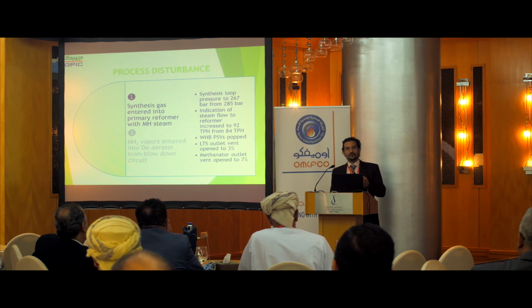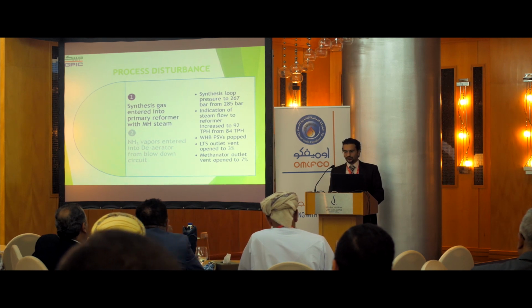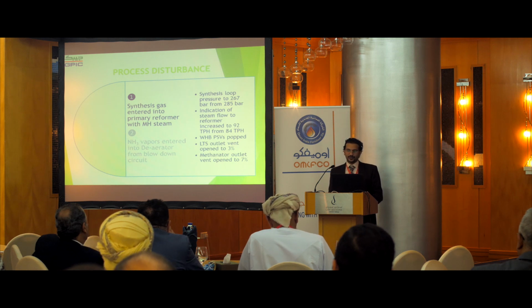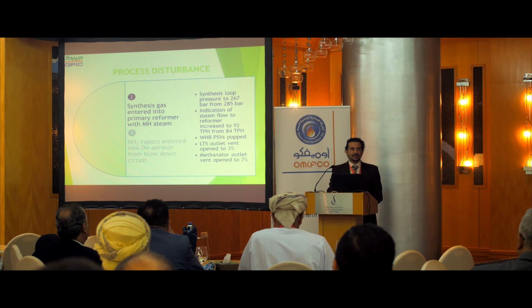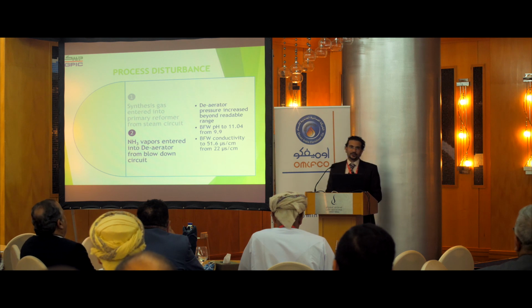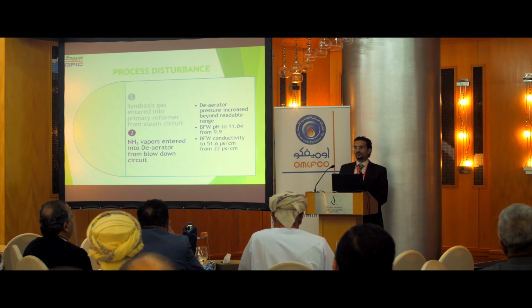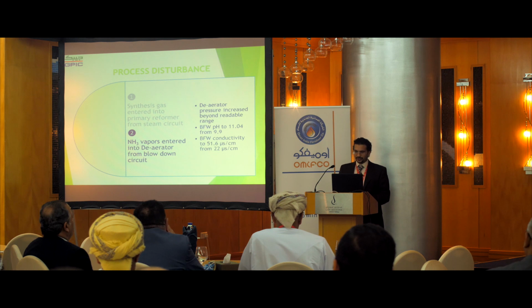The waste heat boiler PSVs, we have 2 PSVs, both popped. The LTS outlet vent, the low temperature shift converter, opened 3%. We have a vent downstream that opened on auto, and the methanator outlet also opened by 7%. The ammonia vapors entered the deaerator from the blowdown circuit, and we could not read the deaerator PSV pressure, it went beyond range. The pH went to 11.04 from 9.9, and conductivity was already high because of our minor or hairline leak, but when it failed, it jumped to 51.6 microsiemens per centimeter.